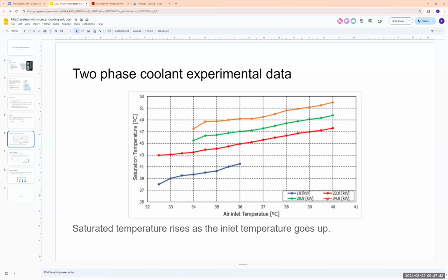One heat exchanger, defined by different air temperatures and different power, and then you get the approach. But if you think about using liquid cooling with one phase, it is almost the same. If you get one heat exchanger, you will also get a similar graph, not with saturation temperatures, but with liquid temperatures. And at the end, you will have an approach.